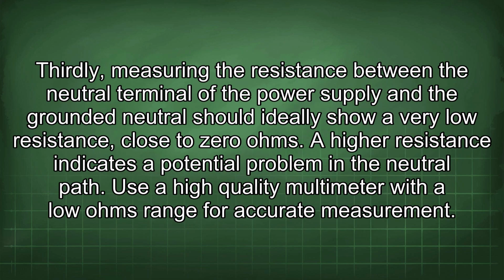Thirdly, measuring the resistance between the neutral terminal of the power supply and the grounded neutral should ideally show a very low resistance, close to 0 ohms. A higher resistance indicates a potential problem in the neutral path. Use a high-quality multimeter with a low ohms range for accurate measurement.